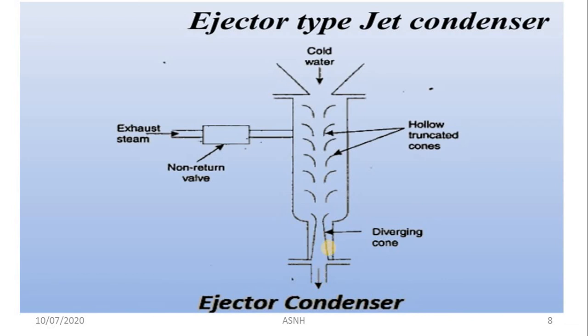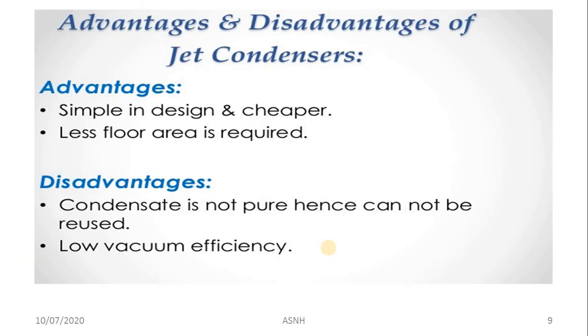The main specialty of all kinds of jet condenser is that mixing of steam as well as water takes place, but it never happens in the other type of condenser, that is the surface condenser. There are some advantages as well as disadvantages of jet condensers. The advantages are that they are simple in design as well as cheaper. The second advantage is that less floor area is required. The disadvantage of the jet type condenser is that the condensate is not pure, hence it cannot be reused. Whatever condensate is available is not reused again because it is not pure. This is the most important disadvantage of the jet type condenser, but it never happens in the case of the surface condenser. In a similar way, low vacuum efficiency is there in the jet condenser as compared with the surface condenser.